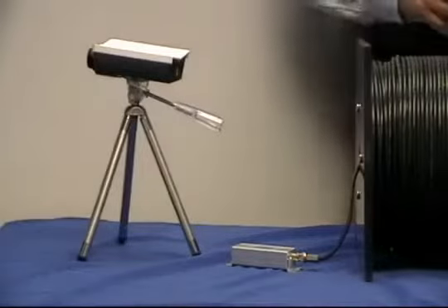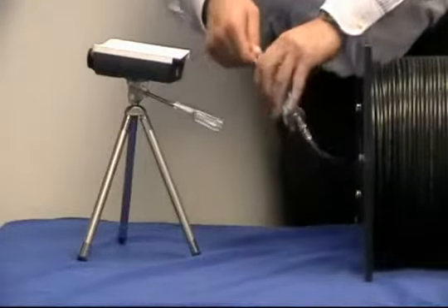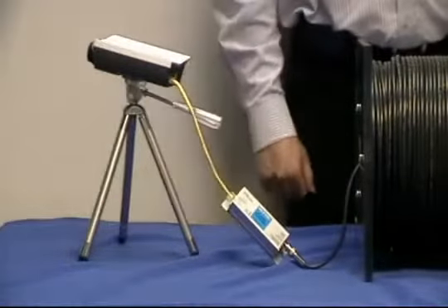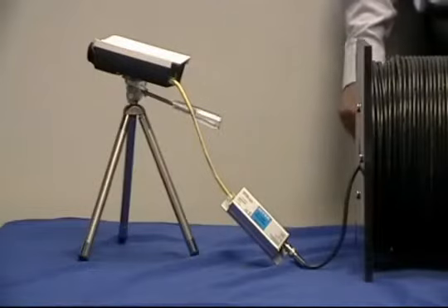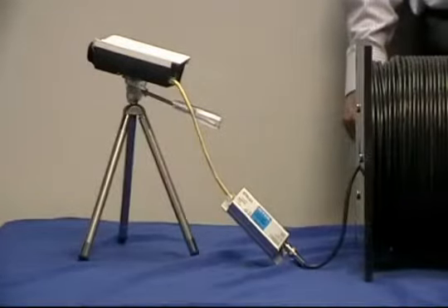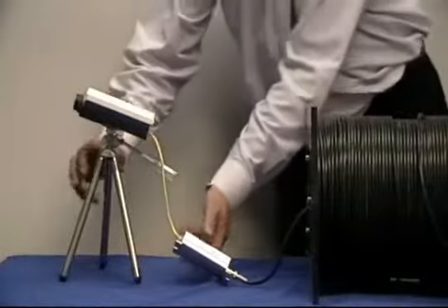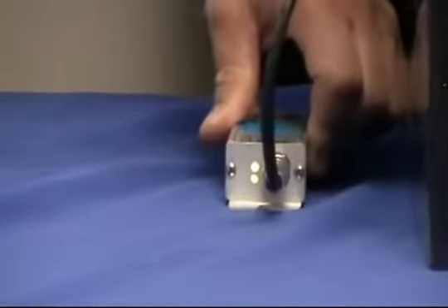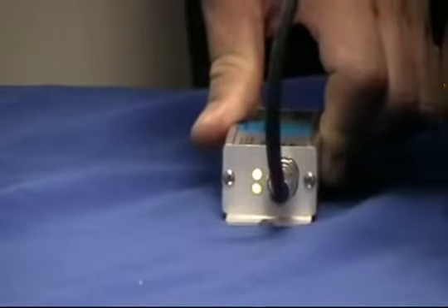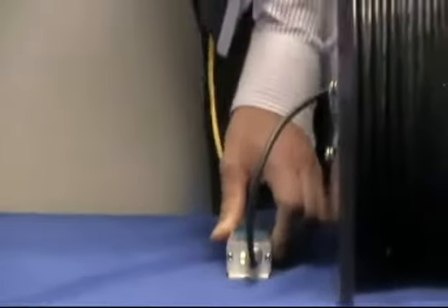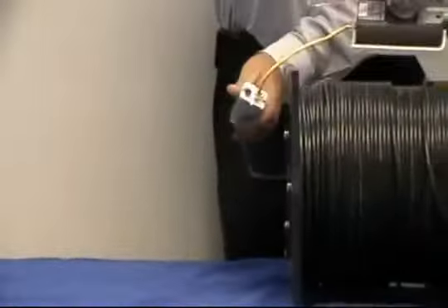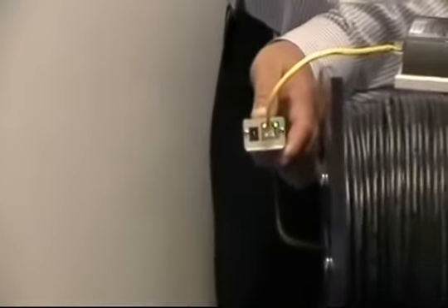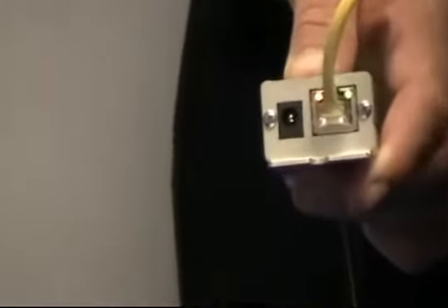The final connection to be made is between the EtherStretch transmitter and the new IP camera. Connecting a computer patch cord between the camera and the EtherStretch transmitter will complete this installation. After the final connection is made, just as with the receiving end, the PoE out light on the transmitter will illuminate, as the connected device has been checked and it has been confirmed that the camera connected is a true PoE device. The amber LED will also illuminate, indicating that a compatible 10/100 network device is currently attached.